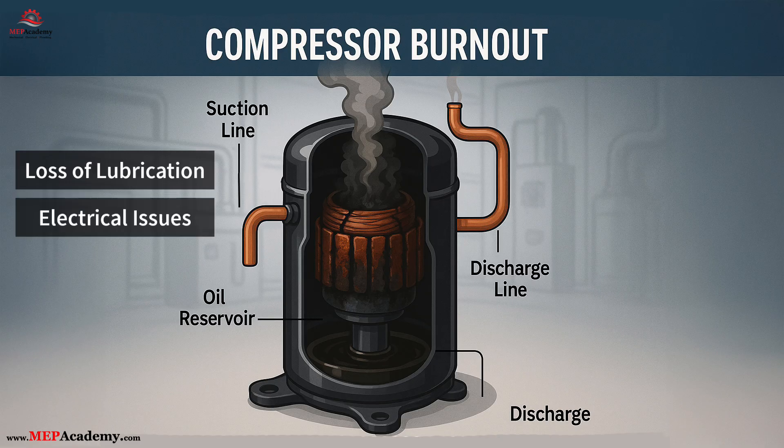Electrical issues like voltage imbalance or short circuits. Short circuits in a compressor typically occur when insulation on the motor windings breaks down due to overheating, moisture, or age, causing electrical contact between phases or to ground.